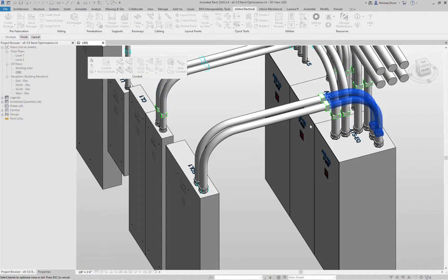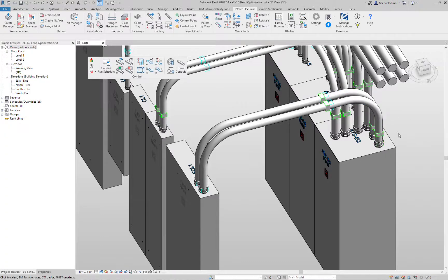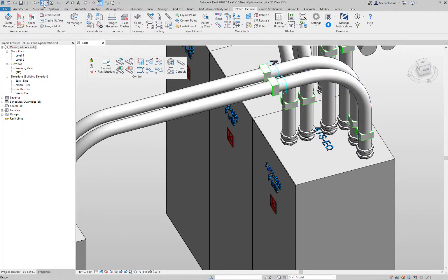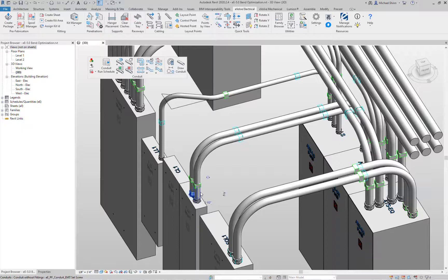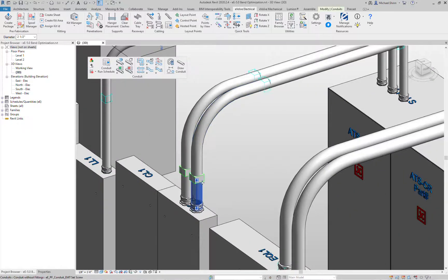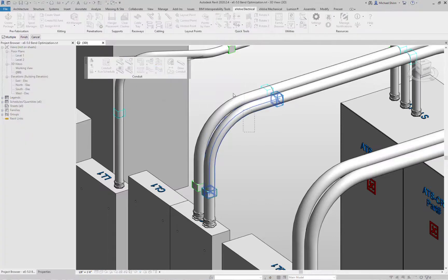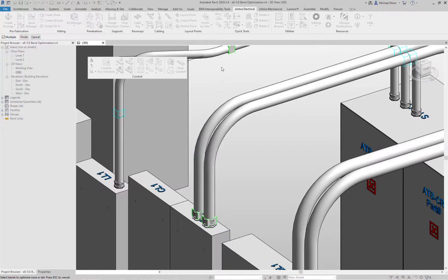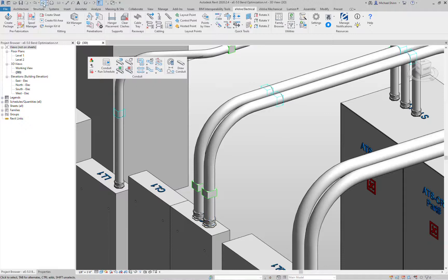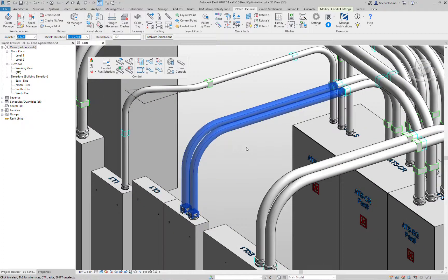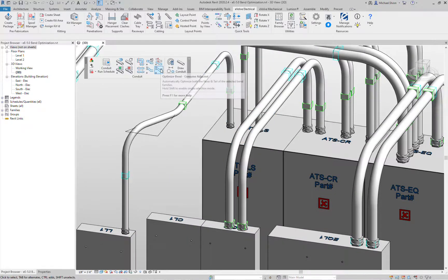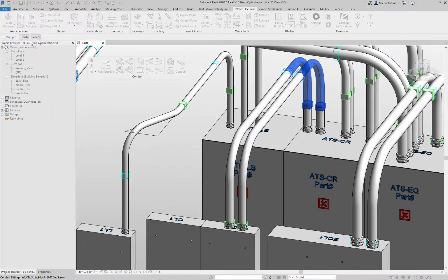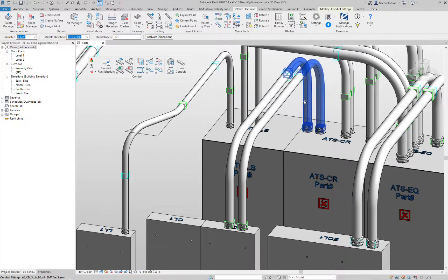I also have the ability to use consume selected, which allows me to pick onto these two bend families, click finish, and say: just optimize this section here — basically remove just those straight pieces. That's what consume selected does: it allows you to select which side of the bend you want to consume. Consume adjacent is going to extend both sides to its maximum available length. Let's click onto these two bends again, click finish — it extends those to its maximum available length, with only a few inches to go in this scenario.